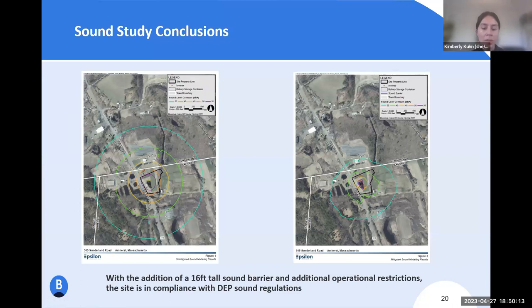From their analysis, our battery storage facility has inverters on pads as well as battery units with HVAC systems that generate some level of noise. In order to mitigate that, we're proposing a 16-foot tall sound barrier that will surround the entire system. In addition, we're implementing operating restrictions so that not all batteries are operating at once. This is done to make sure that at the property boundaries we're still in compliance with the DEP sound regulations.